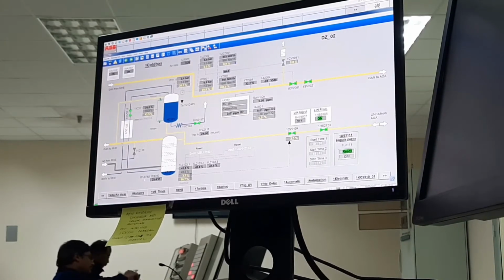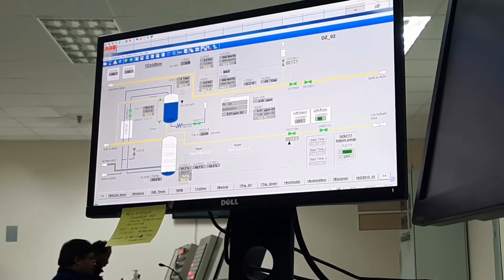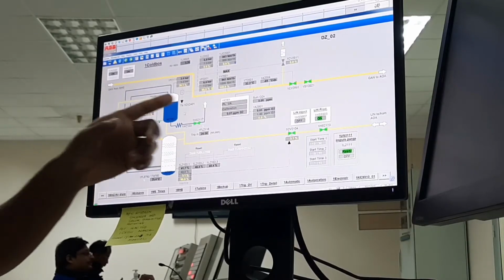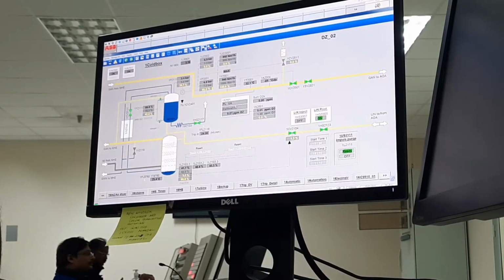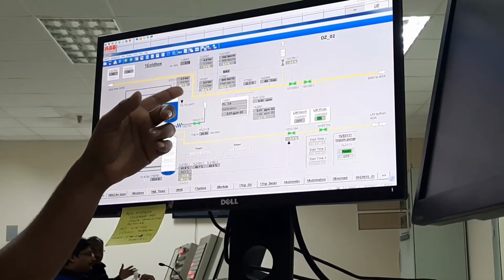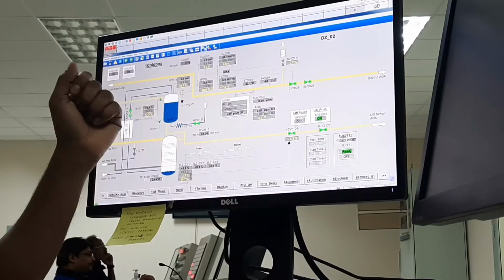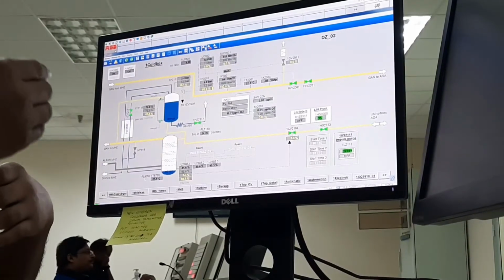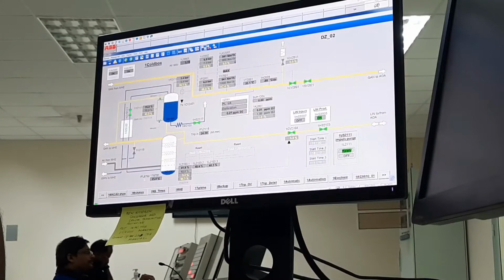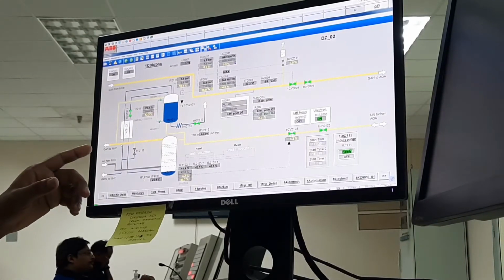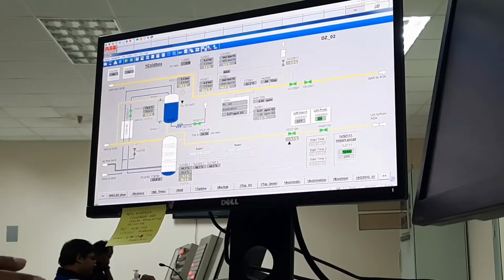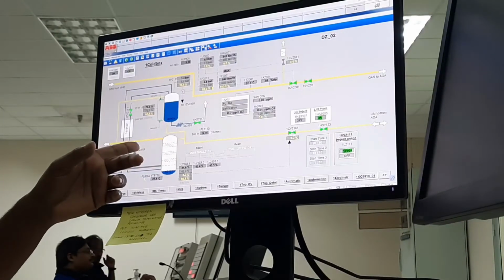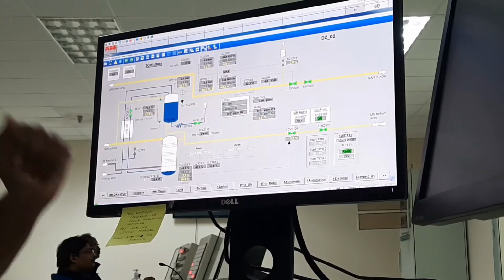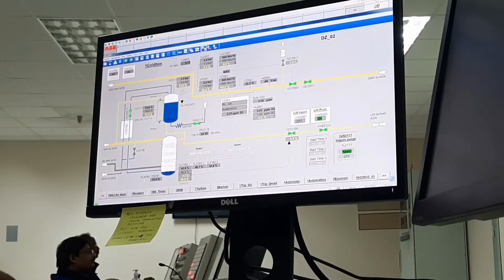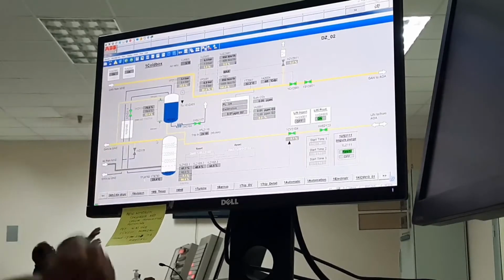What is this? This product will go in two lines. One line goes to this condenser and another line goes to the main heat exchanger. After that it will go to the gaseous nitrogen product. So our target for gaseous nitrogen product, we have kept a set point of 1000. We can produce gaseous nitrogen at 1000 normal meter cube per hour. By this line, total product is 3000 normal meter cube. But this gaseous nitrogen we are producing now is 1000 normal meter cube, while our product is 3000 normal meter cube.